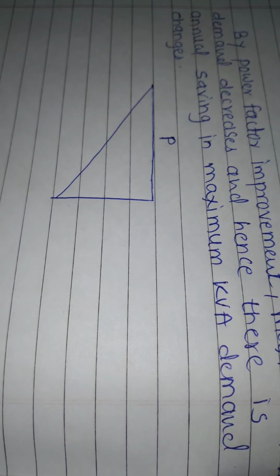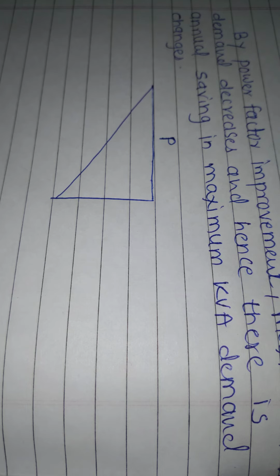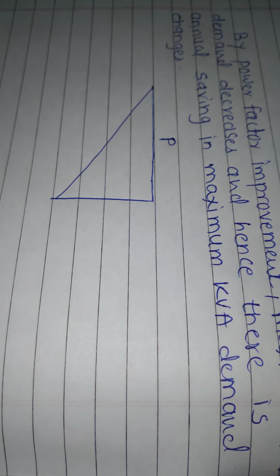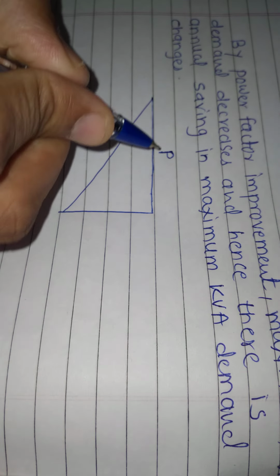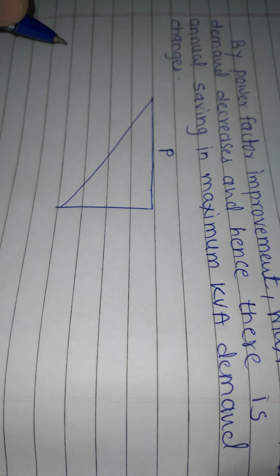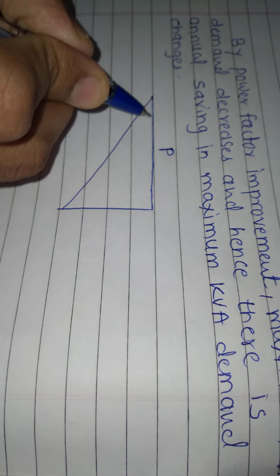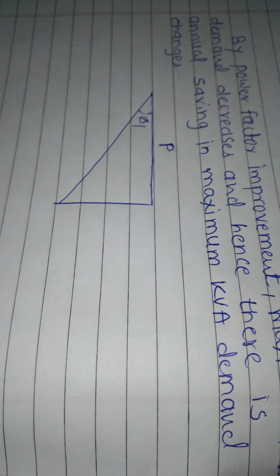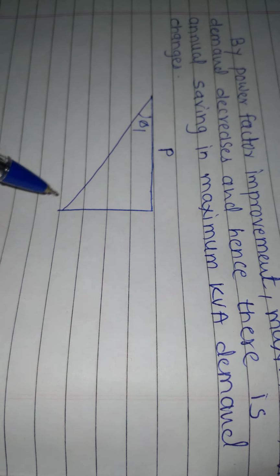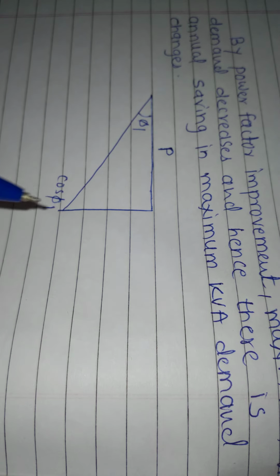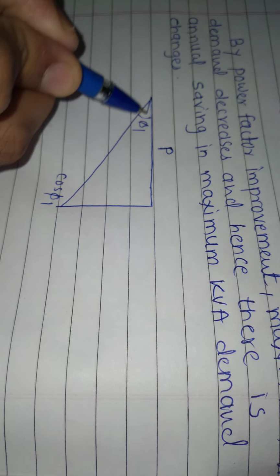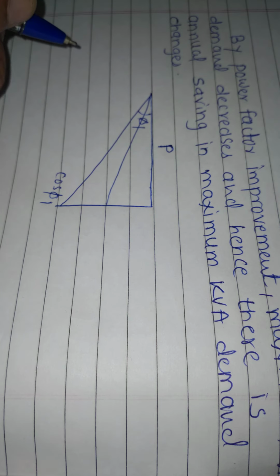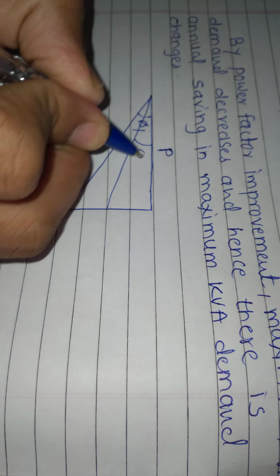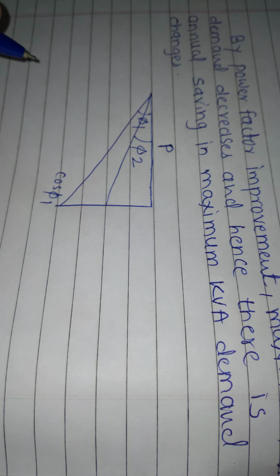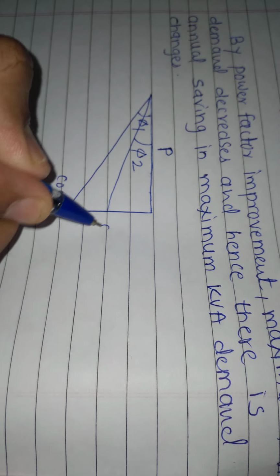A consumer takes kilowatt maximum demand, constant, represented as P, and the load is operating at power factor cos phi 1, having kVA rating based on cos phi 1. Because of installing power factor improvement equipment, let us assume power factor improves to cos phi 2, and now the kVA demand decreases to cos phi 2.